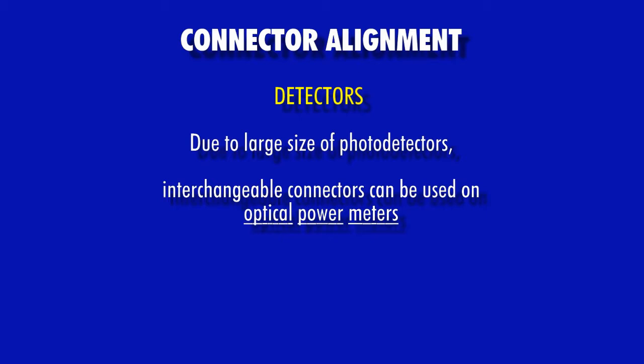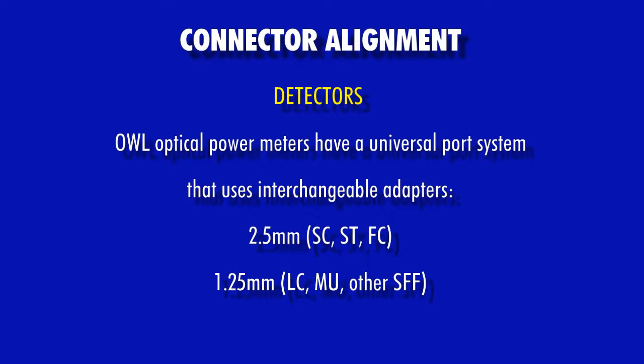This is why it does not matter whether or not an optical power meter uses interchangeable connectors. In fact, OWL optical power meters utilize interchangeable universal connectors, one for 2.5 millimeter ferrule connectors such as ST, SC, and FC, and another for 1.25 millimeter ferrules such as LC, MU, and other small form factor connectors.